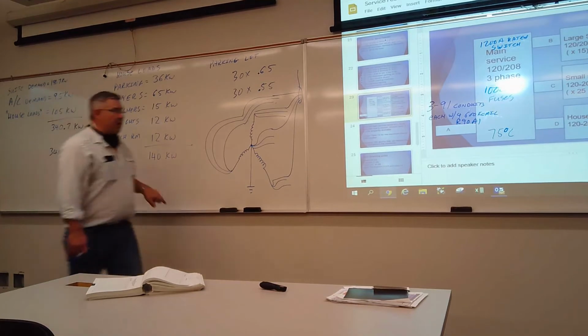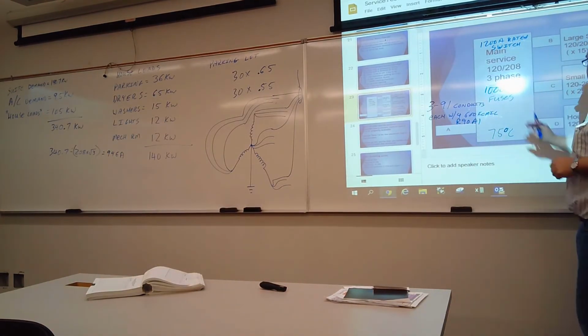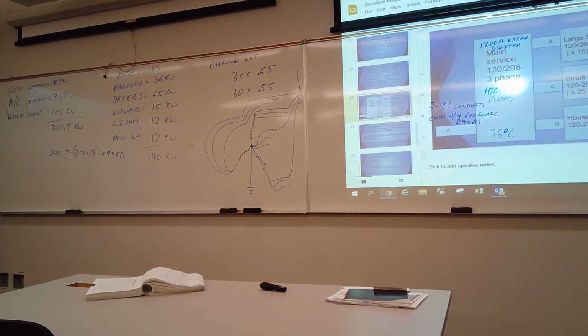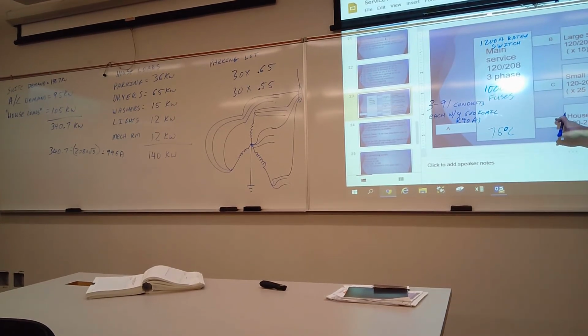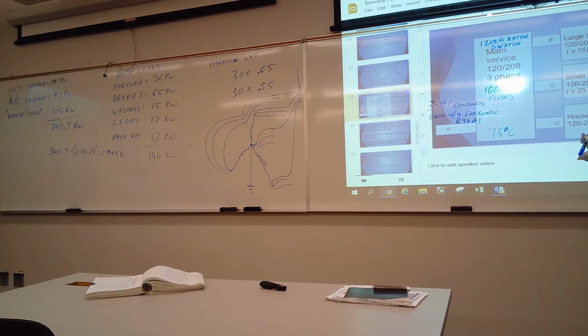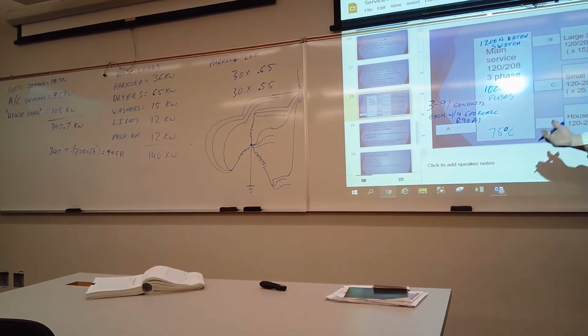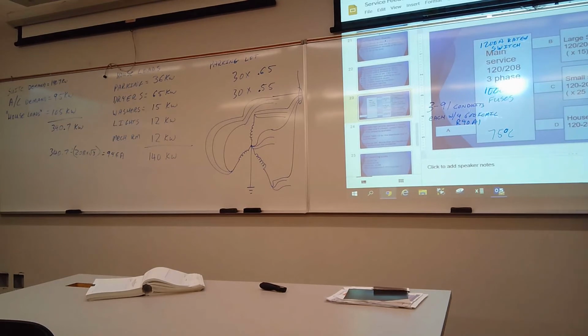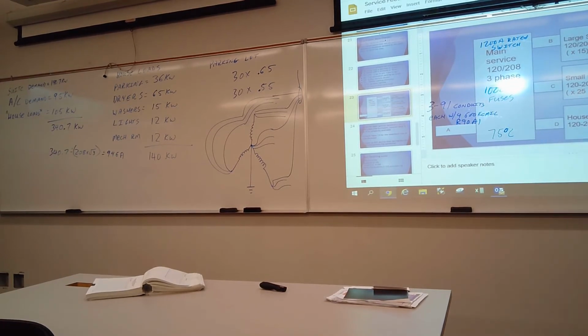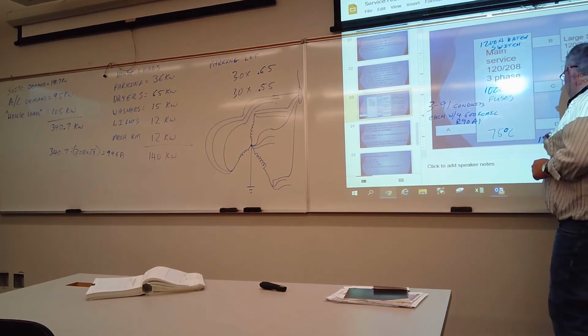The reason being is that this conductor right here, going from our distribution up to the house panel, right? It's going to go through a splitter, fuse, disconnect, and all that kind of stuff. I just broke this down to kind of bare bones for simplicity. These conductors right here have to be able to carry the full 140 kilowatts, right? Not the 105. Reason being, well, if people are downstairs doing laundry, they're probably not cooking. So, you know, if the house panel loads are being utilized to the max, there's probably some individual suites who are using less than we've allowed. So at point D right here on this map, we're going to have to size these conductors for 140 kilowatts.